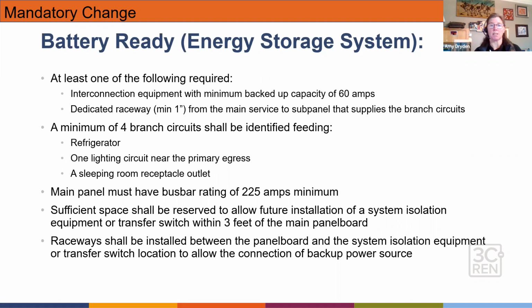So you can see here we have interconnection equipment with a minimum backup of 60 amps. We have a dedicated raceway, so that's 1 inch, from that main service to any sub panels that supply the branch circuits. And we're looking at a minimum of 4 branch circuits that should be identified in that feed: a refrigerator, a lighting circuit, and a sleeping room receptacle. So those are at least 3 that need to be identified, and you're going to get a 4th. This is really looking at ensuring battery ready that will also provide assistance in power outages for critical loads. Our main panel must have a bus rating of 225 amps. Our main panels are 200 amp rating for the capacity, and so the bus bar capacity we just want to ensure is 225 amps.